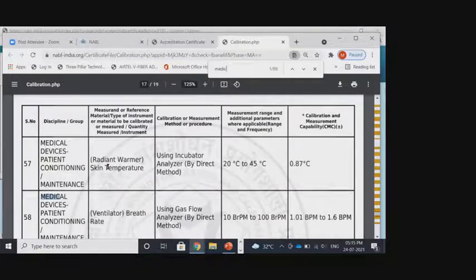If we see, this is the scope for medical devices for this particular laboratory, radiant warmer. Here the parameter is skin temperature. The calibration method is using an incubator analyzer by direct method. This is the range of calibration, and this is the calibration and measurement capability of the laboratory. So like this, you can search for laboratories, and then you can approach the laboratory for calibration of your equipment.